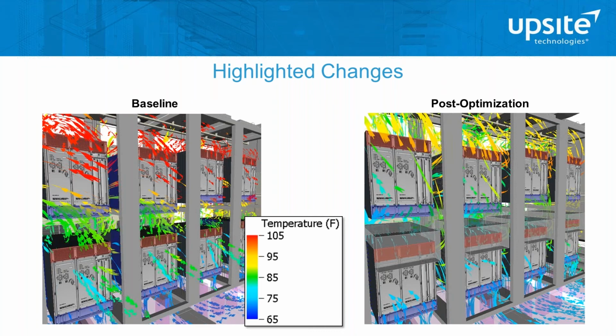What we had to do was come up with new baffling systems that created a much more acceptable situation. You can see the airflow changing quite dramatically, and the inlet temperatures dropped considerably, by 20 degrees or more in this particular case.